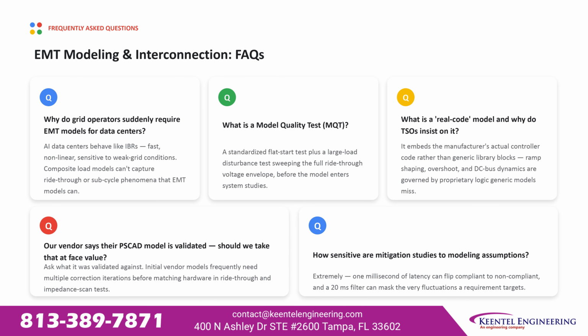Why do grid operators suddenly require EMT models for data centers? Because AI data centers behave like inverter-based resources, fast, nonlinear, and sensitive to weak grid conditions, and composite load models simply can't capture the ride-through or sub-cycle phenomena that EMT models can. What is a model quality test? It's a standardized flat start test plus a large load disturbance test that sweeps the full ride-through voltage envelope, run before a model ever enters system studies.